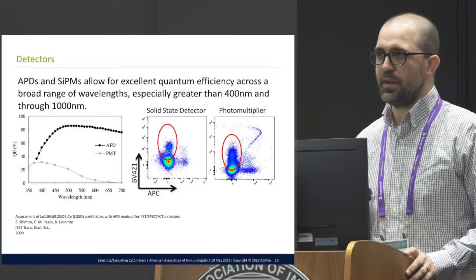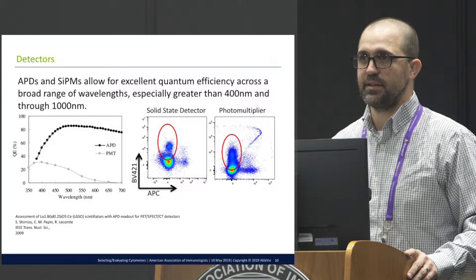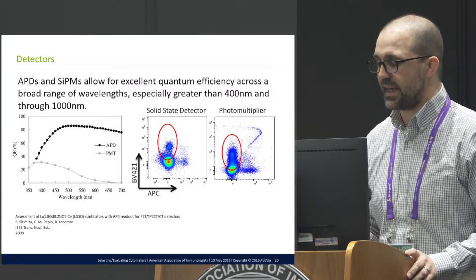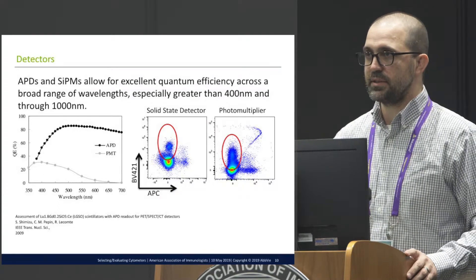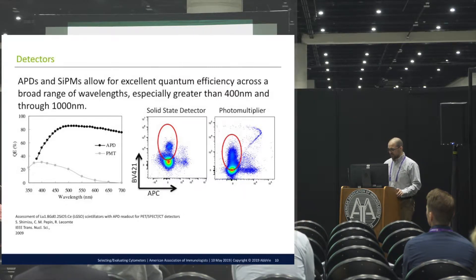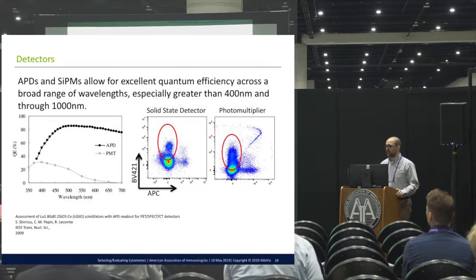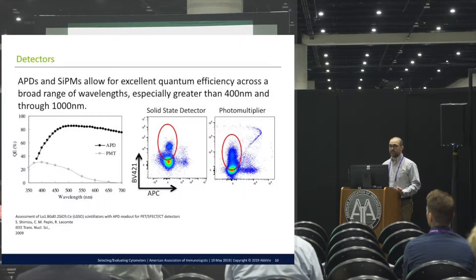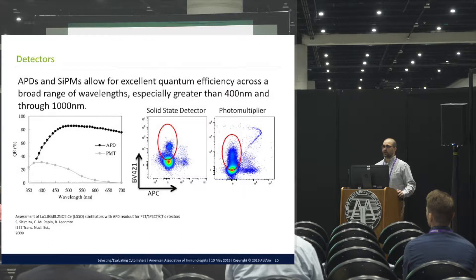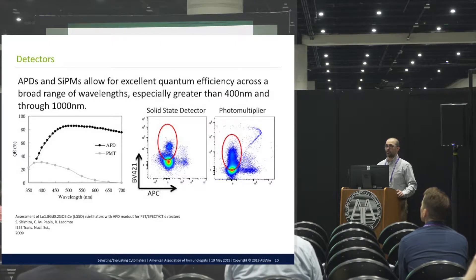In terms of detectors, one of the main advances many companies have made is using solid-state detectors, specifically avalanche photodiodes, or in the case of the Quanteon, an array of diodes in a silicon-based photomultiplier. The result is basically the ability to have greater quantum efficiency over a wider range of wavelengths on your flow cytometer. Quantum efficiency measures how efficiently a detector converts incoming light photons into an electrical signal measurable by downstream electronics. Photomultiplier tubes perform pretty well in the higher-energy, lower-wavelength range.